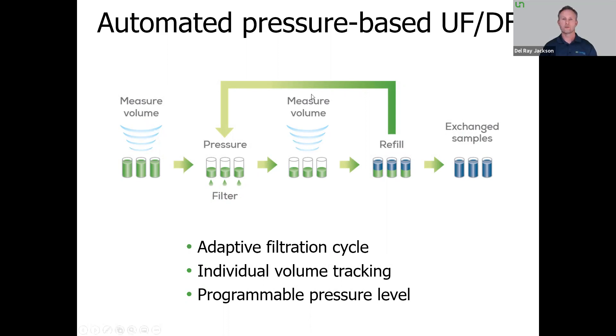The next part is our approach: automated pressure-based ultrafiltration and diafiltration. This approach is different and superior. It starts with measuring the volume of each individual well in an Unfilter, and you'll see why this is so critical. As we go into our buffer exchange cycles, we apply a uniform pressure across the entire Unfilter. The key part is that each buffer exchange cycle is adaptive — we re-measure the volume of every single individual well to essentially negate the possibility that you might dry out and lose one of your precious samples.